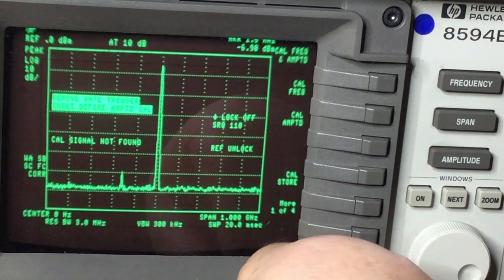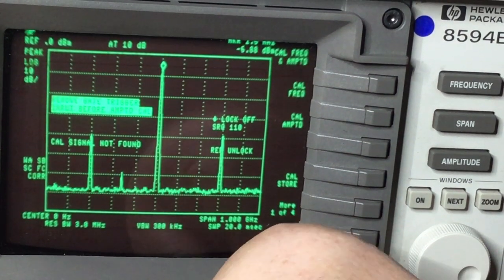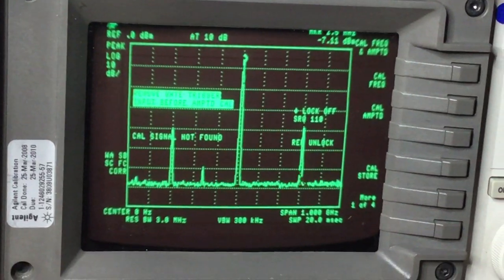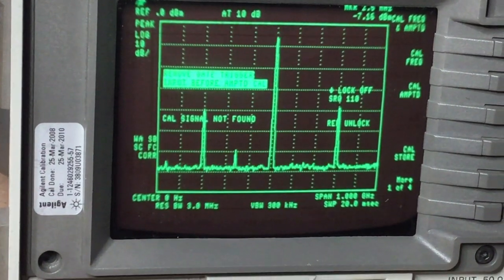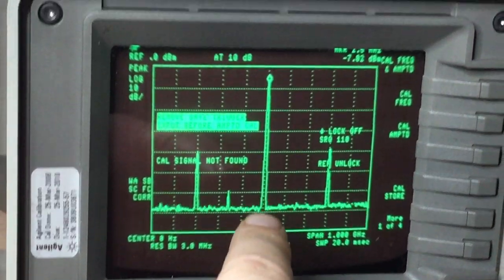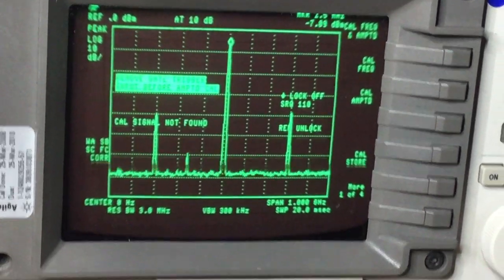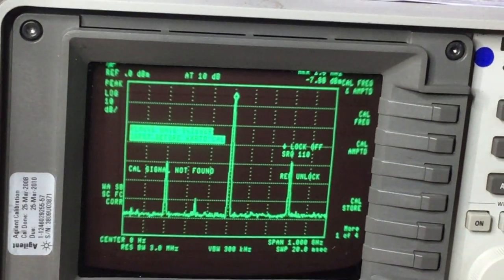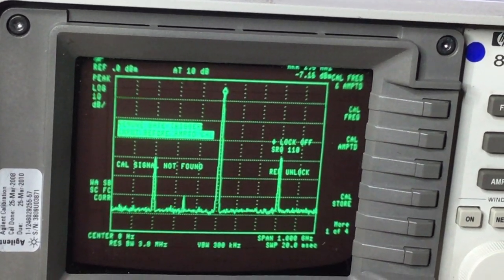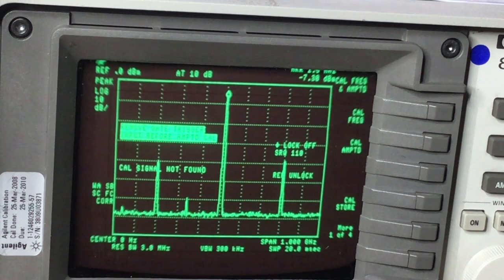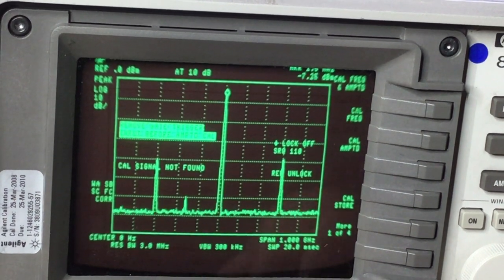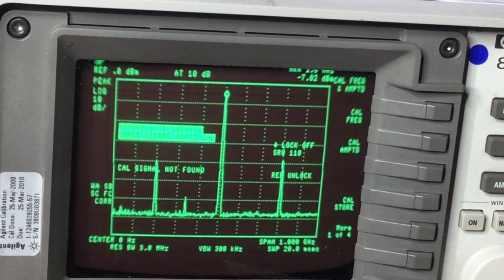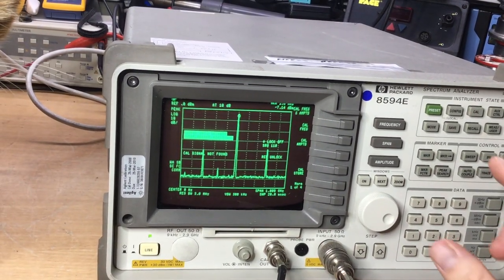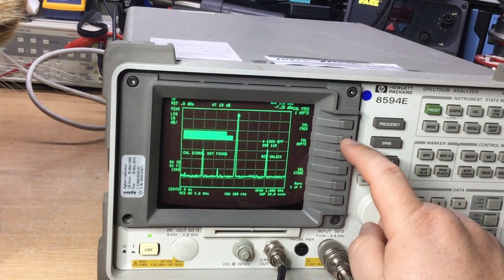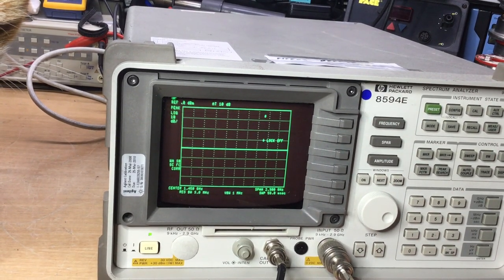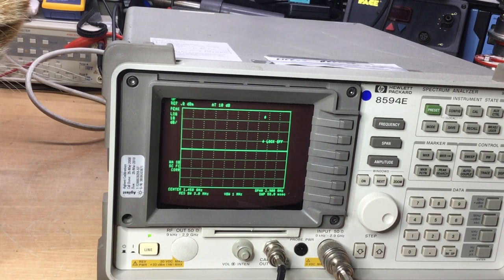We've got something there, it's come back, might be a bit dirty. Is that signal maybe? Because it does the other say that the center frequency is 0 Hz. So this is the internally generated signal that we get with the HP Agilent spectrum analyzers. This is often seen, as I've remarked in previous videos before about that. So what we can do anyway is we can go back to the calibrate menu. We'll just do a cal amplitude just to see whether that does anything, and we'll see what happens there.